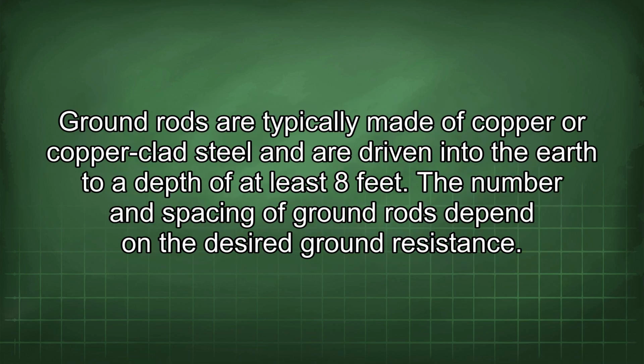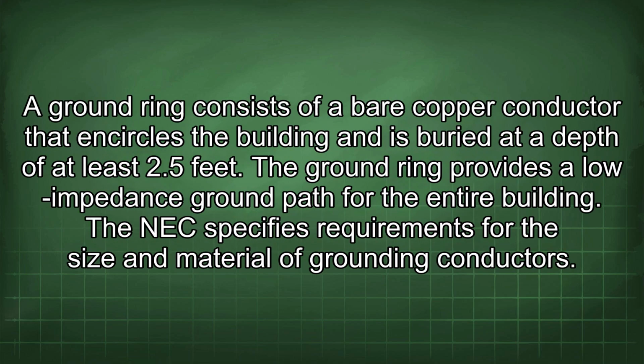Ground rods are typically made of copper or copper-clad steel and are driven into the earth to a depth of at least 8 feet. The number and spacing of ground rods depend on the desired ground resistance. A ground ring consists of a bare copper conductor that encircles the building and is buried at a depth of at least 2.5 feet. The ground ring provides a low impedance ground path for the entire building.